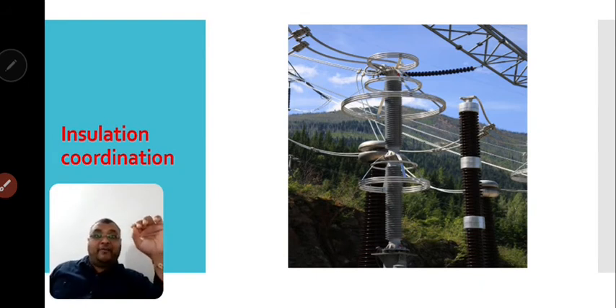And when designing equipment with proper insulation coordination, the economic design of a reliable substation requires a study of various over voltages. So whenever you design this equipment, you must consider the study of different over voltages, such that insulation will be subjected to switching transients, fault conditions, power frequency resonance conditions, or lightning impulses.